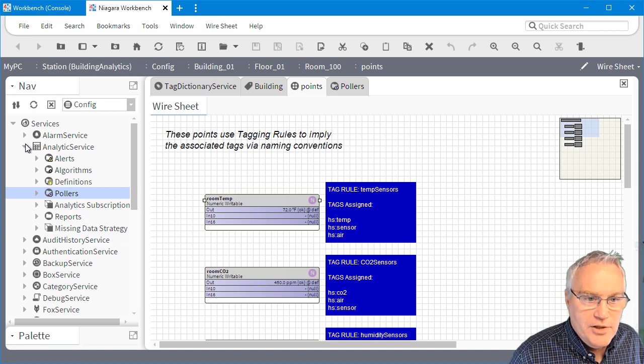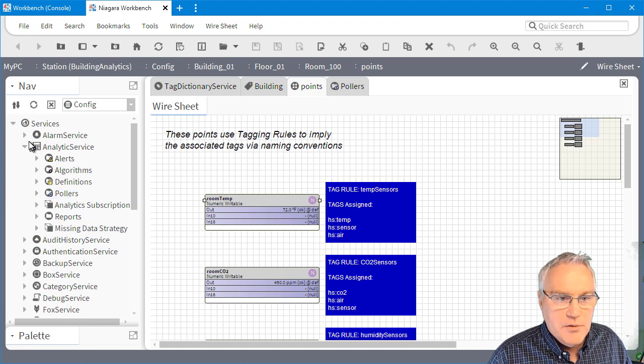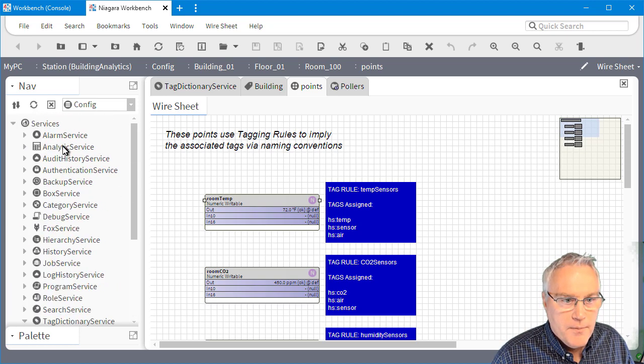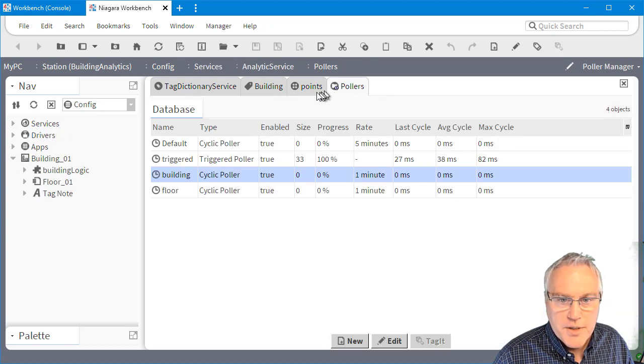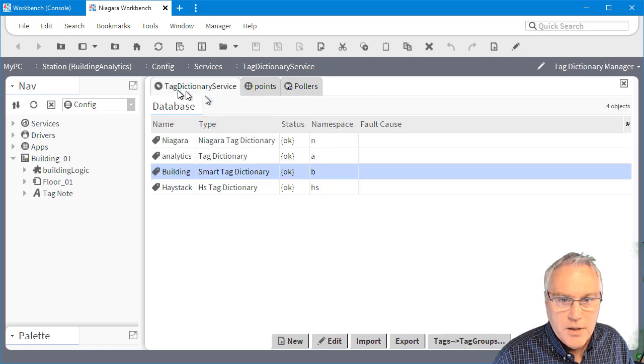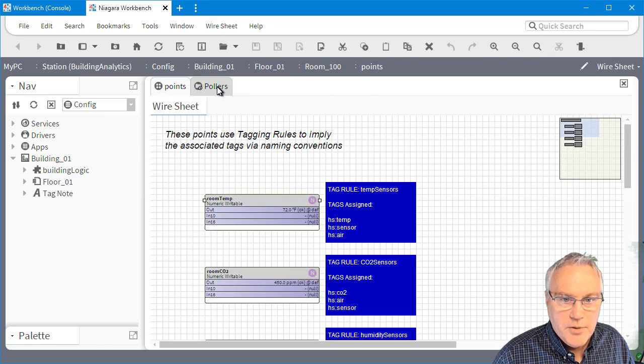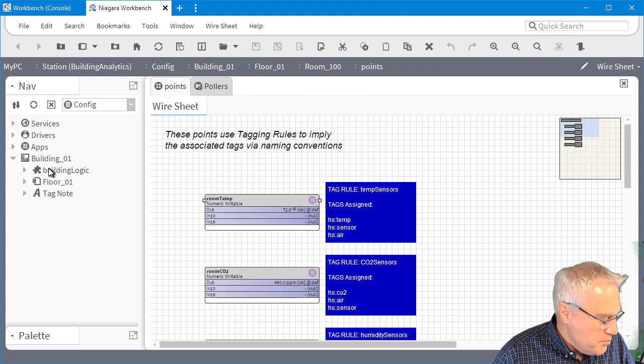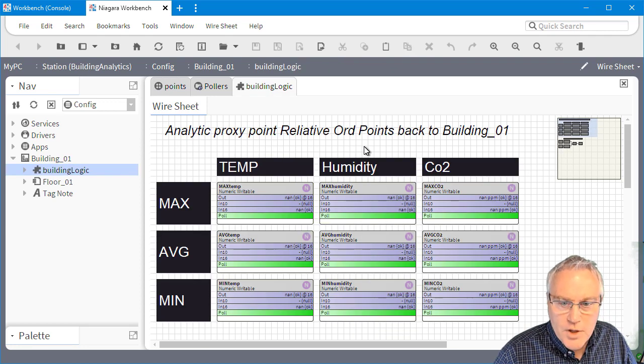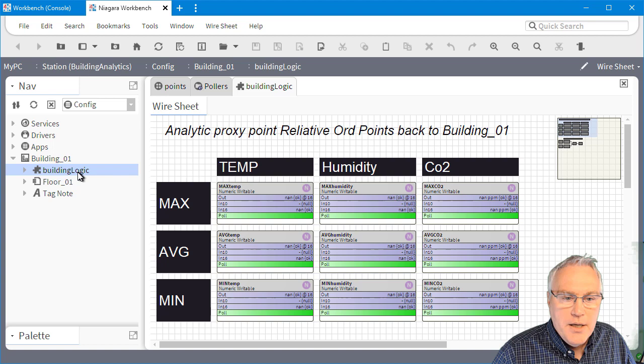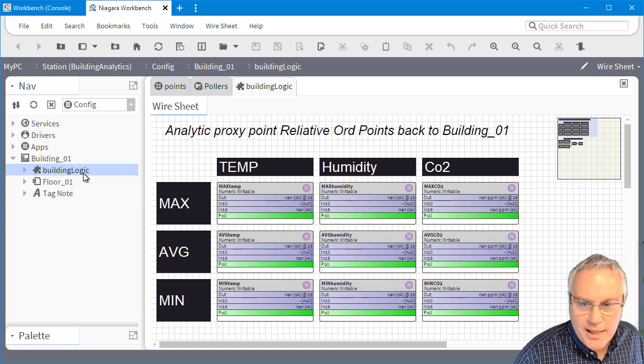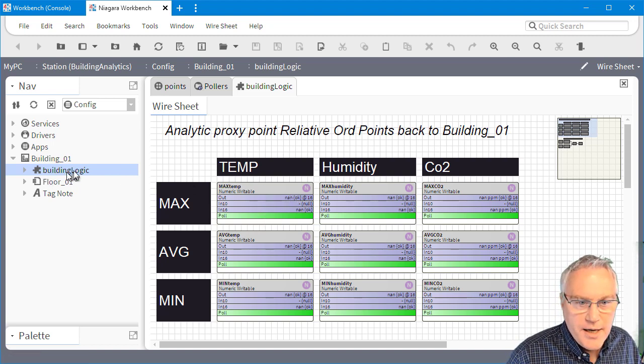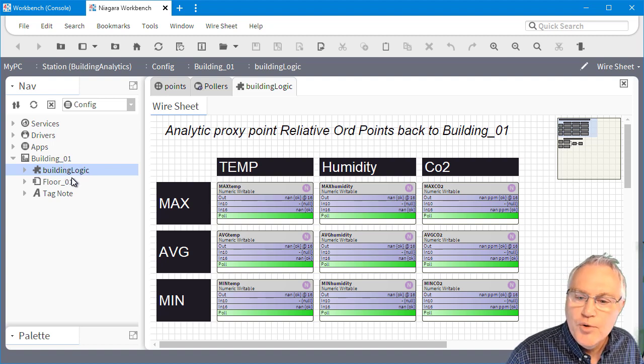So with that, let's take a look at how the building looks. If we come down here to close the services down, look at our building. I'm going to make sure the pollers are always there so we can close this tab, close this tab, go back to our points. So poller is there. If we come down here to the building logic, you'll see that the way I break this up is I've kind of figured out and made it my best practice that any analytic proxy points, I expose the poll slot. And then I've kind of regulated to creating my analytic logic in its own folder. That way it's easily templatable.